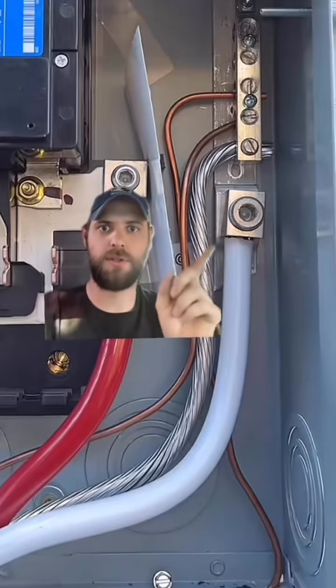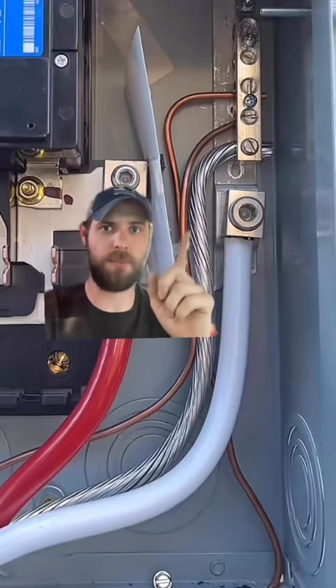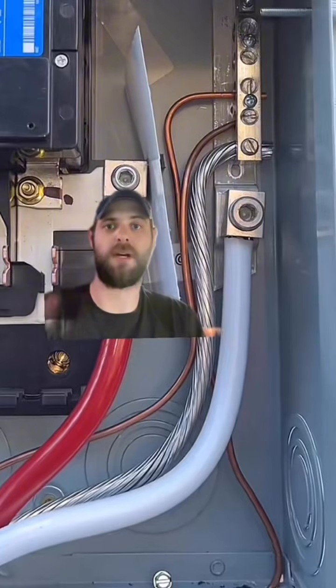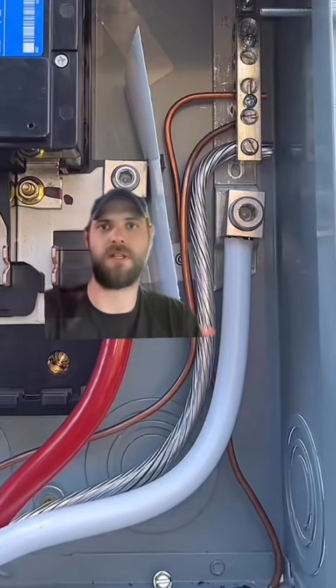So in conclusion, your neutral and equipment grounding conductor only get bonded together once per system, but you better bond them together if you want any hope of your breakers tripping in the event of a ground fault.